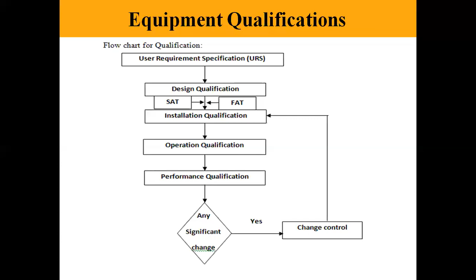As per QMS requirements, you raise the change control. Then you initiate the installation qualification. After completion of the installation qualification, go for the operation qualification, then the performance qualification. During the performance qualification, if you want to make any significant changes in the particular equipment, you go for change control. Then whatever stages of the qualification are required can be done, and you follow the further steps.